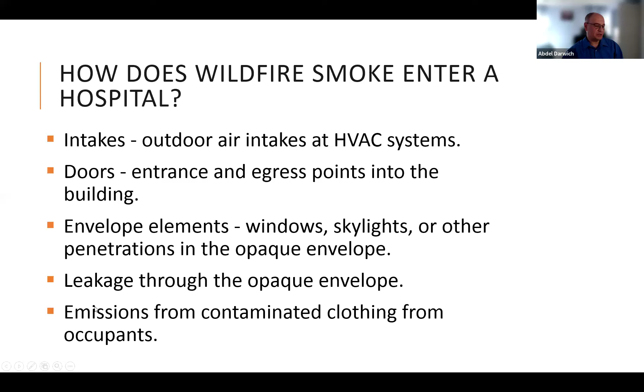So how does wildfire smoke actually get into a hospital or a building? First, the outdoor air intake at your HVAC system. Second is the doors, the envelope elements, the windows, the skylights, and other penetrations in the opaque envelope. Then leakage through the walls. People don't know it, but there could be leakage in the walls that you don't see. And if your building is negative, well, here you go, you're sucking smoke in. Last is the emission from contaminated clothing from occupants. This usually happens in the ED or other areas, and usually the HVAC system cannot do much about this last point, so I will not go over it in detail. So let's start with the first one, outdoor air intake.